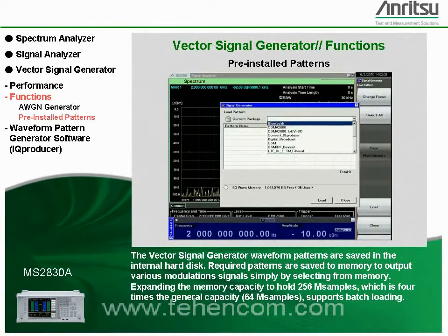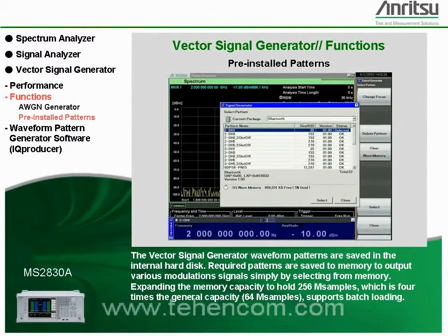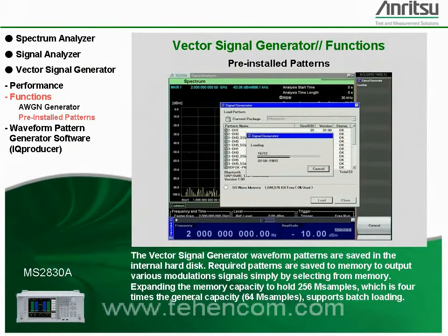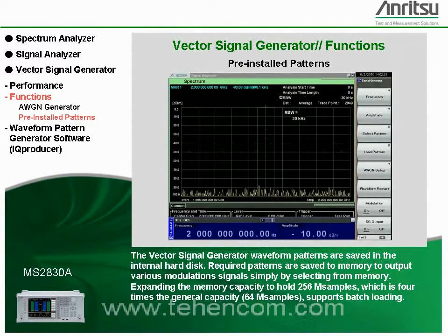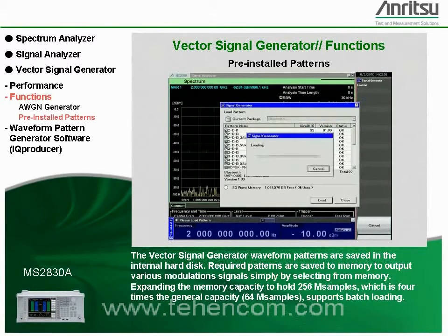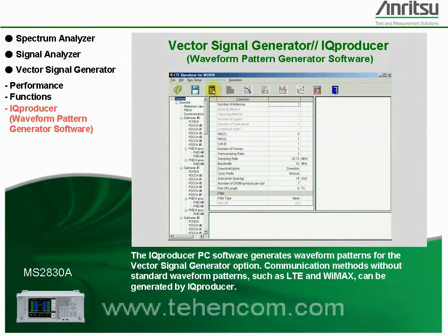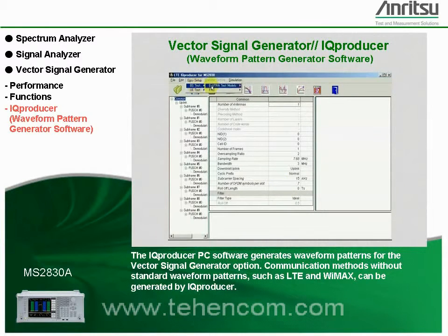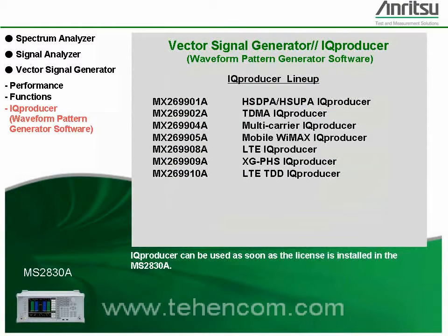The vector signal generator waveform patterns are saved in the internal hard disk. Required patterns are saved to memory to output various modulation signals simply by selecting from memory. Expanding the memory capacity to hold 256 mega-samples, which is four times the general capacity, supports batch loading. The iQProducer PC software generates waveform patterns for the vector signal generator option. Communication methods without standard waveform patterns, such as LTE and WiMAX, can be generated by iQProducer. iQProducer can be used as soon as the license is installed in the MS2830A.